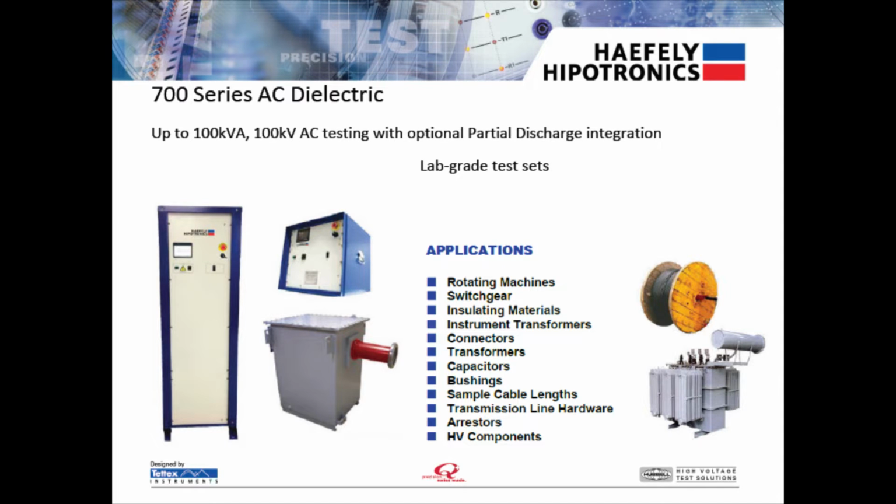So for a PD measurement, you need a power source to power up the transformer, and you need the ability to hipot test. So here's pictured our 700 series AC dielectric testers, which as standard go up to 100 kVA, 100 kV, but if you ever worked with us, we can make larger customized systems if you desire.